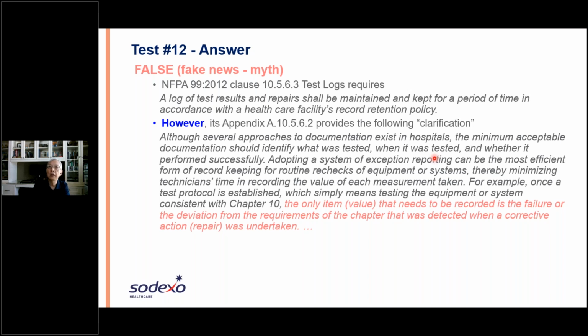And when you have a litigation in your hands and the plaintiff's lawyer says, how come you released a piece of equipment that was out of range? You are going to be in a very tough situation to answer that question, because how do you know that it was fat-fingered wrong or it was indeed an out-of-range number? Unless you have an automated way to collect that number and put it into your CMMS, don't even bother to do it, because you are not required to do it. But if the number is out of range, you need to record it, because then you need to fix it, okay?